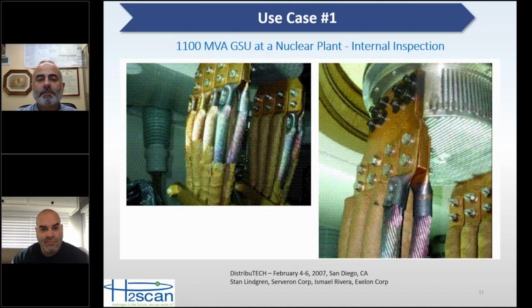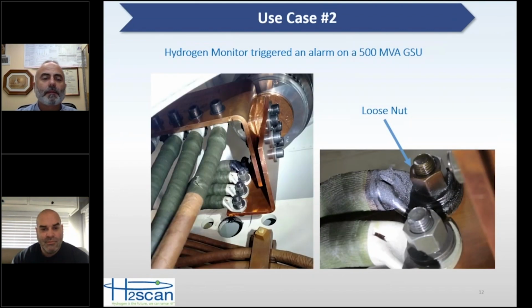And then the next case is a 500 MVA GSU. Now, in this case, they only had a hydrogen monitor. The hydrogen monitor went into alarm. Over a 2-week period, they took 3 oil samples. By the 3rd oil sample, they were seeing acetylene.